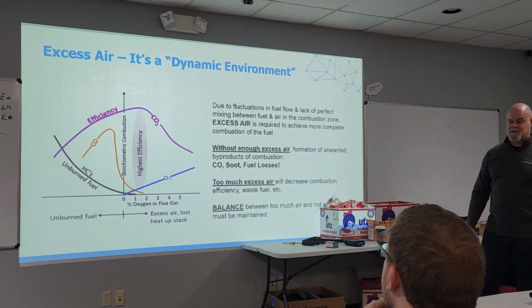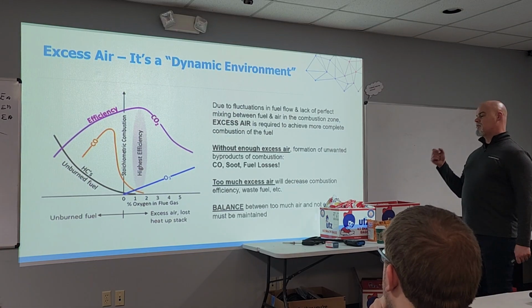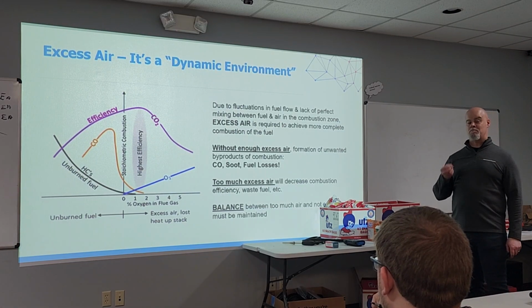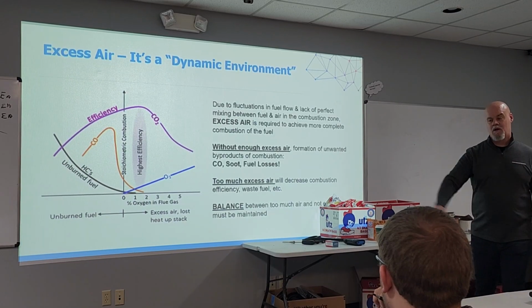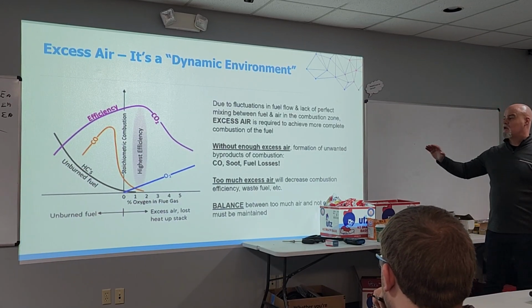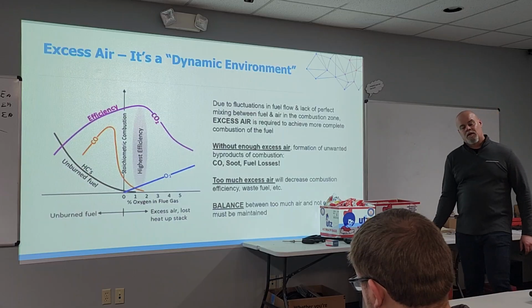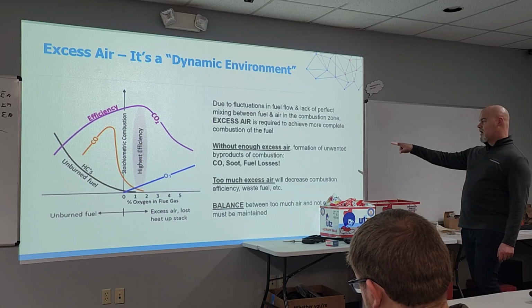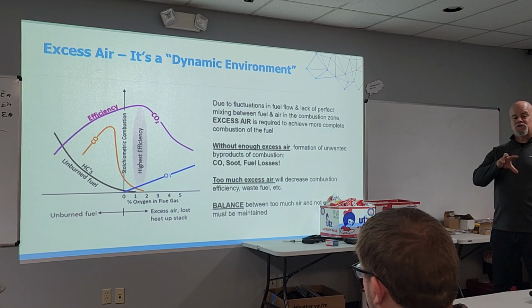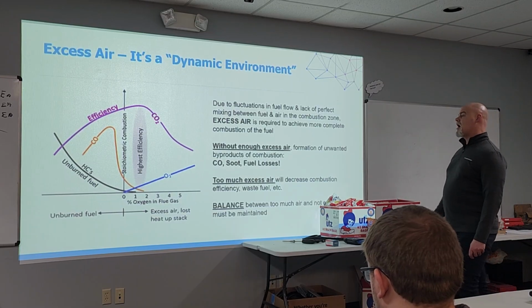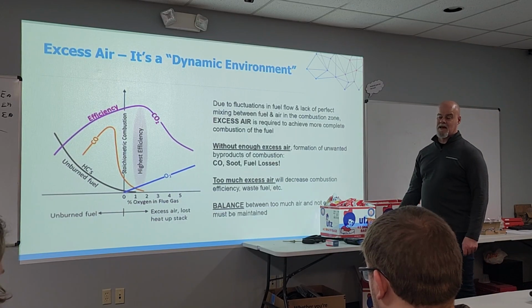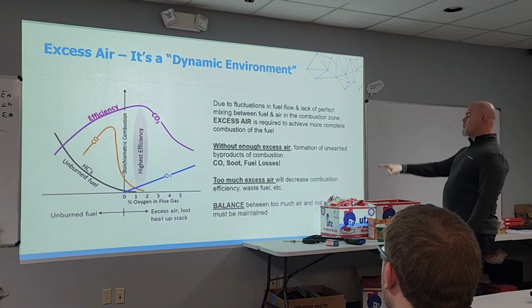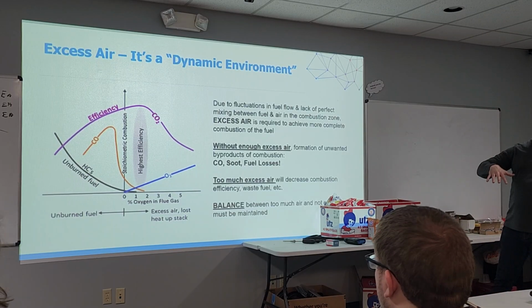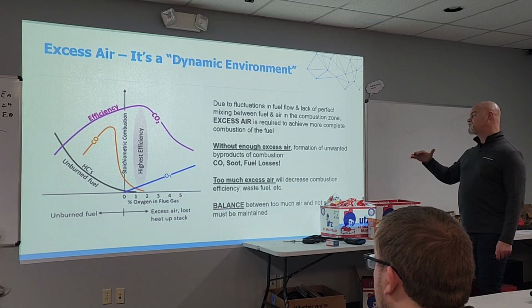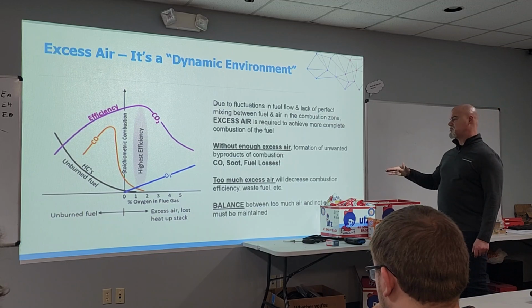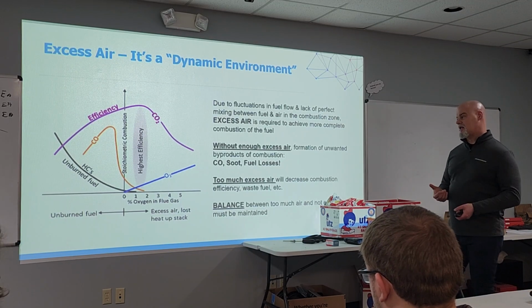In this case, our friend is excess air. Excess air is brought into the combustion process because we have inadequate mixing between air and fuel. So we need to bring in a little excess air to balance that out, to give it a bit of oomph. Without enough of it, we produce soot and CO conditions, high or overly high stack temperatures, and overfired systems. But with too much excess air, we're thinning it out too much, wasting fuel, and decreasing our combustion efficiency. So the goal is to strike a delicate balance.